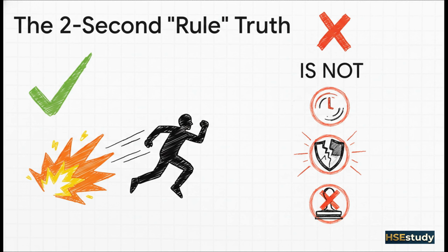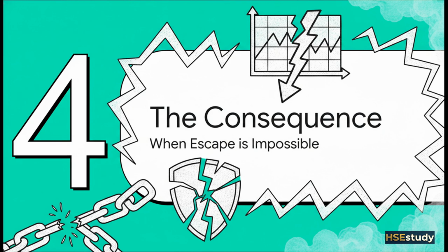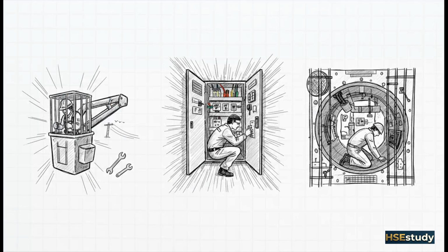It is not a guarantee that you're safe, and it absolutely is not something that should be applied automatically to every calculation. The arc doesn't care about a 2-second assumption. It's going to burn as long as that breaker lets it. So what happens when that core assumption that a worker can actually escape is false? What happens when it's not physically possible? The consequences are catastrophic because the calculation that was used to pick out their PPE was based on a complete fantasy. And let's be honest, these scenarios are everywhere.